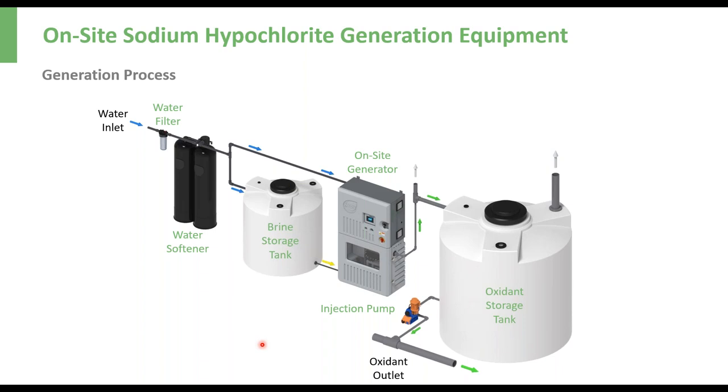So we have soft water mixed with the granular salt, and that's dissolving into a solution to make a brine solution. And what's cool about this is nature's great at making a stable, consistent concentration. So when you put soft water and salt together, if you see salt left over, you still have what we call fully saturated brine solution. Fully saturated brine solution runs, I'm going to say, roughly 26%. So 26% salt can go into solution, and that's what we call fully saturated.